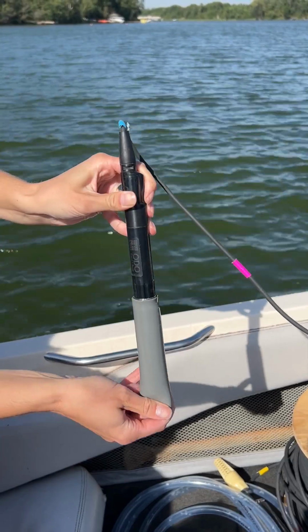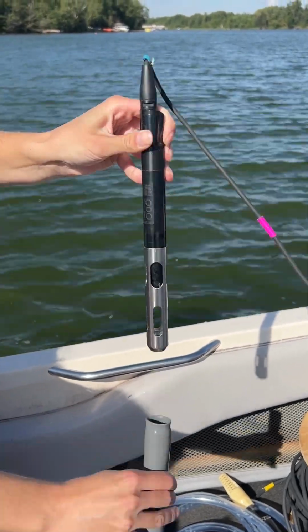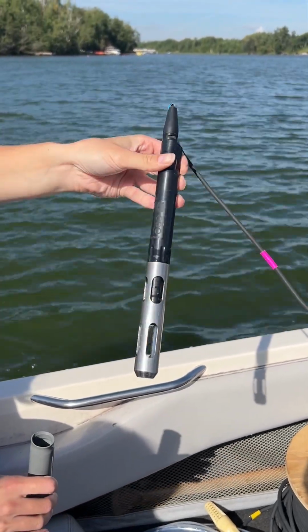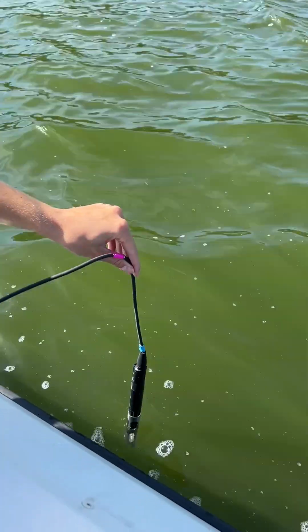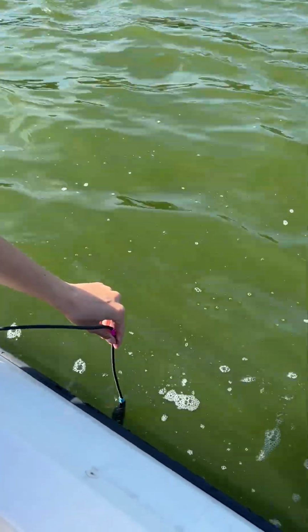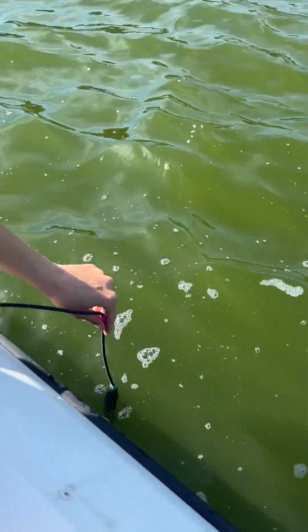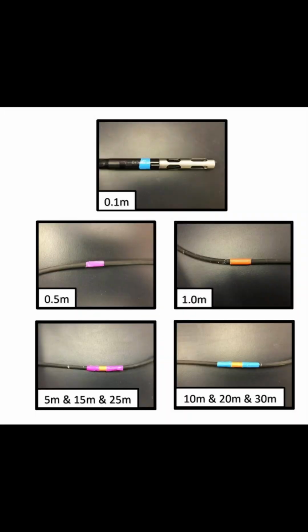Next, we will get our probe ready to take our probe measurements. So we will remove the gray sleeve and lower it in so that the conductivity sensor is just below the surface of the water. This is our marking guide that's taped on the probe. So you can find this in your field manual to refer back to it. But each color marking represents a different measurement on the probe.